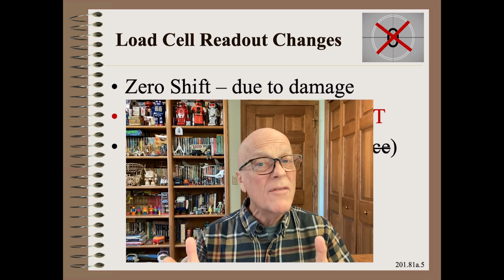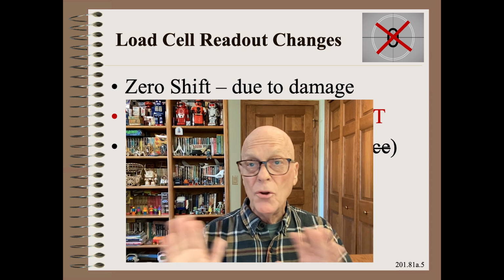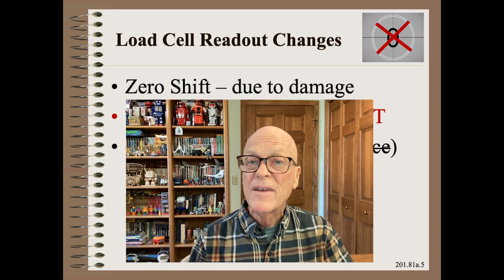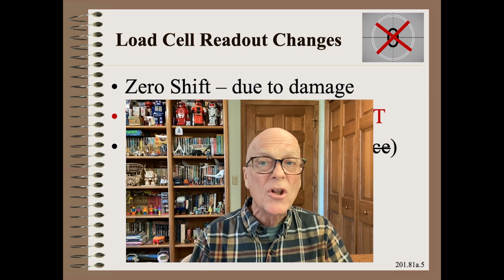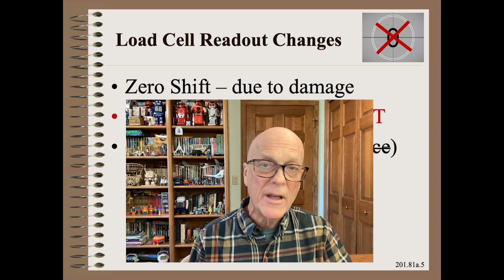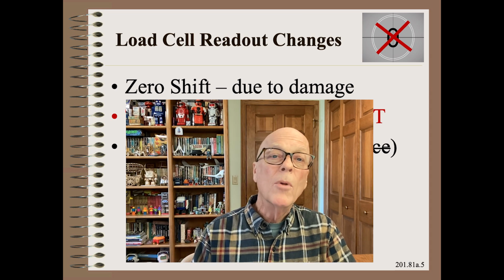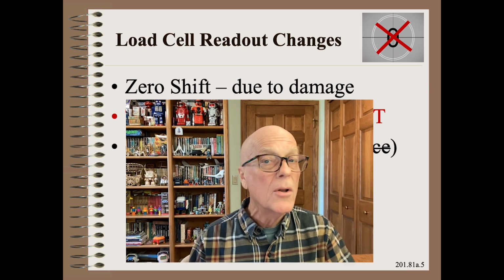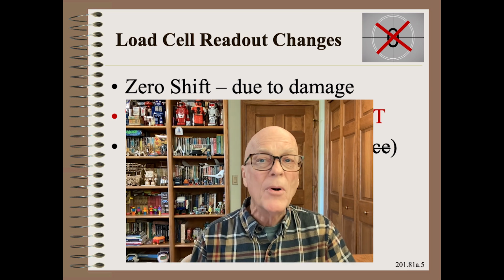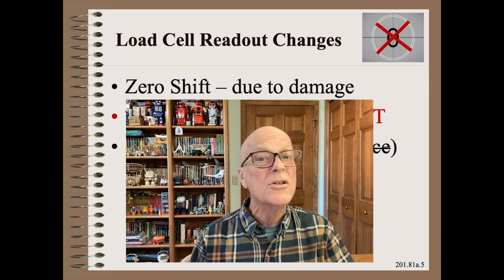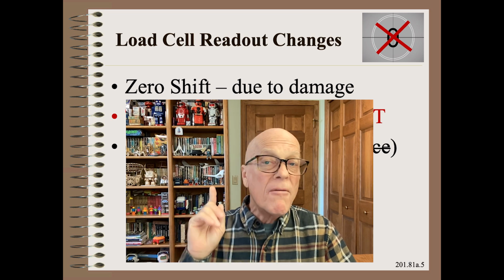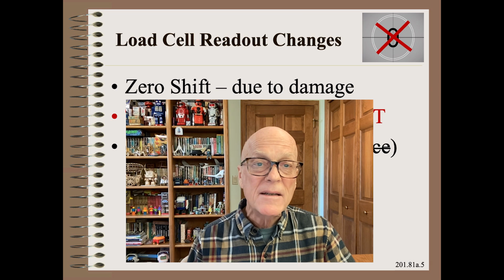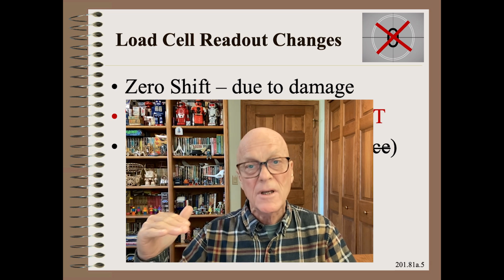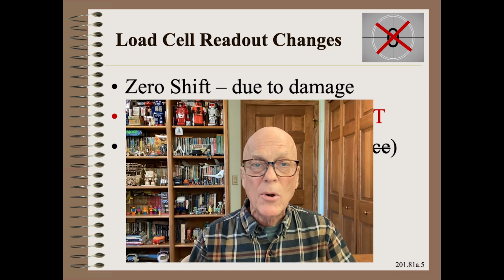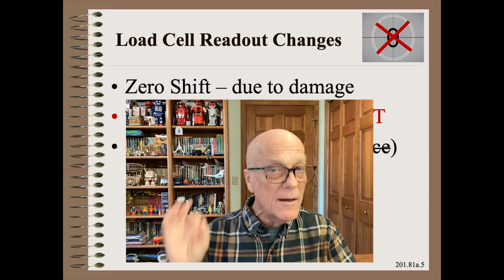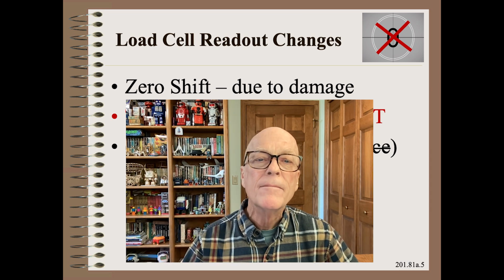Now before we move on, I should add a side note of caution. That is, even if the gauge reads zero, you may not be seeing a negative tension if that were what the load cell was erroneously putting out. For example, most amplifiers will not put out less than zero. For example, most analog gauges do not go below zero. For example, most PLCs have upper and lower limits sprinkled throughout their programs. A lower limit of zero is common.